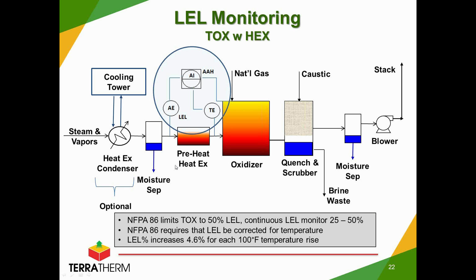NFPA 86 also requires that the LEL sensor and reading is adjusted or corrected for temperature. And whenever you've got a heat exchanger like this, you can see in this diagram, the LEL sensor is on a cooler portion of the vapor ducting. These devices often can't handle the higher temperature of the preheat, so for practicality reasons, the sensor needs to be located in a cool location, but then auto-corrected for the preheated temperature to make sure that we don't read a closer-to-ambient reference LEL and actually have a much higher and unsafe condition because of the preheat. You need to make sure that you're monitoring and alarming to that correction for temperature.